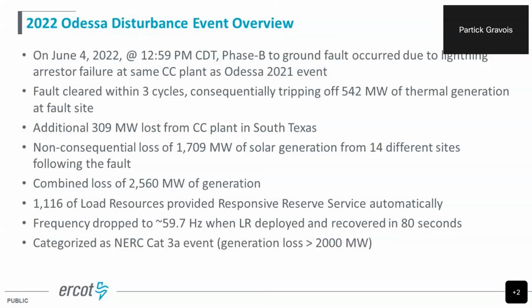For this event, we had a non-consequential loss of about 1,710 megawatts of solar. So we had a nearly 50% increase in the loss of solar from roughly identical events that were 13 months apart. We knew this was a concern.